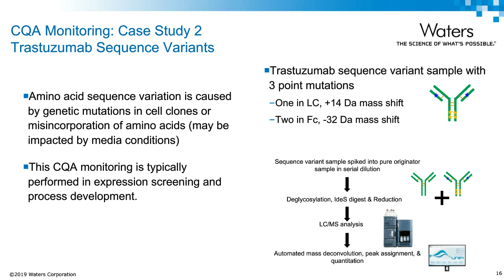Now on this slide, you can see some of the data that came out of this example. On the top, you see the 3 very well separated subunit species: Fc, light chain, and Fd. And below, you can see the peaks correctly assigned by UNIFI after deconvolution. The sequence variants are correctly identified, and then UNIFI will also calculate those out for us in relation to the parent. As you can see on the right side, we plotted the linearity of the serial dilution results, and we have nice linearity and reproducibility in this range from about 1 to 50% variant.